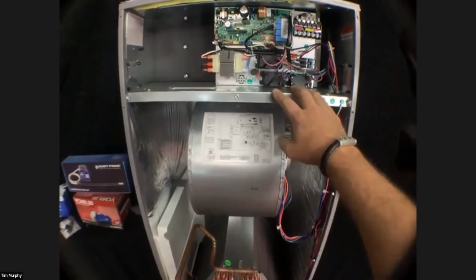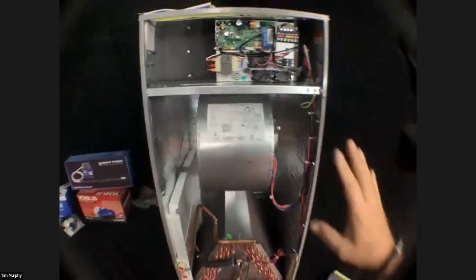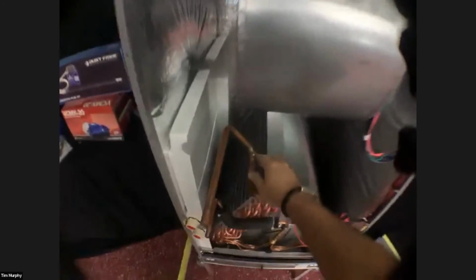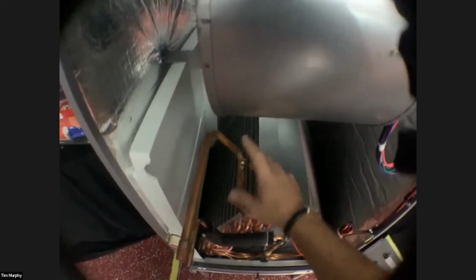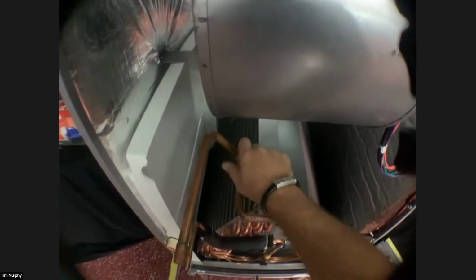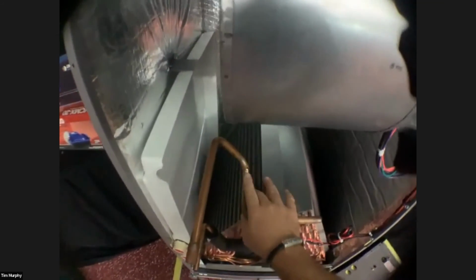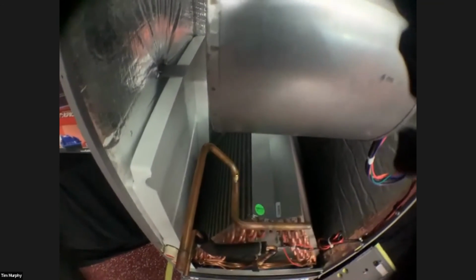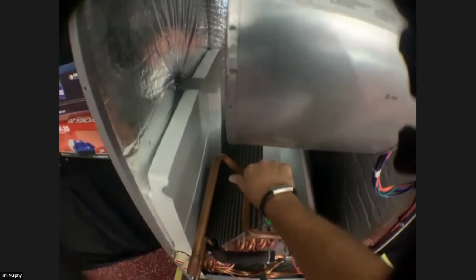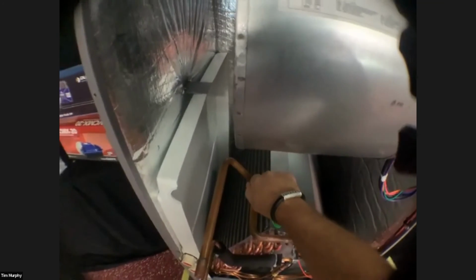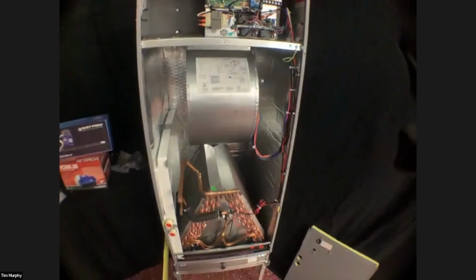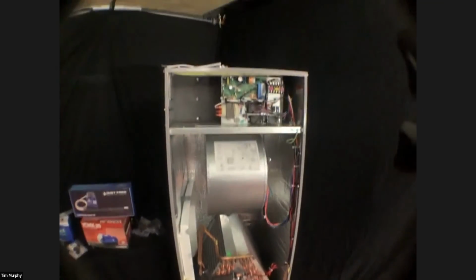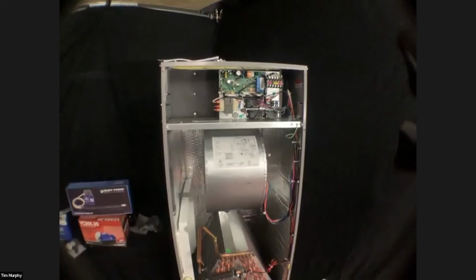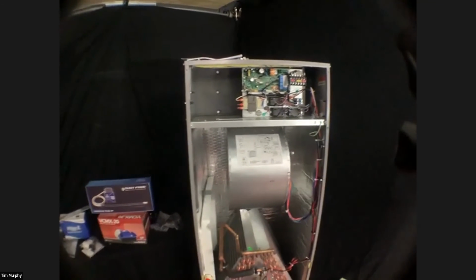For the most part, that's about it when it comes to this system. You do have an access port here if you want to pressure test the coil, or make sure the system has pressure before you start it. If you need to put your gauges on, you have another access port here. It has a Schrader valve in there, so there is another port for you to access the system. Other than that, I don't think I have anything else to say, and that's kind of rare.